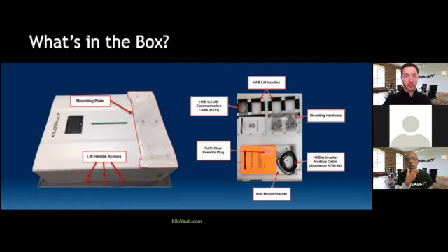So moving right along, we'll start with unpacking. Like I mentioned, it's a heavy battery. So it comes with the mounting plate you'll see on top, lifting handles, and those attached to the screws you can see in the bottom left there, the image. Also comes with all the hardware and then a couple COM cables. So important to note here, in the top left, you have your HAB-to-HAB communication cable, which with a single HAB, you won't need. Also, we have our resistor plug, which with a single HAB, you won't need. Those are only for multi-stack HAB systems, and I'll touch on that more in a second.